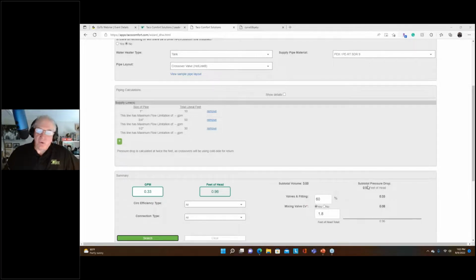So yeah, the question obviously, and I hope we addressed it earlier, but I'll address it again, is, well, that's dumb because you're going to get hot water in the cold water line. No, we're not, because of the operation of the hot link valve. When the hot water arrives at that valve, at that last fixture, it snaps closed almost instantaneously. So we will not have any more passage of hot water, of any water from that hot water line to the cold water line. And understand how this works.